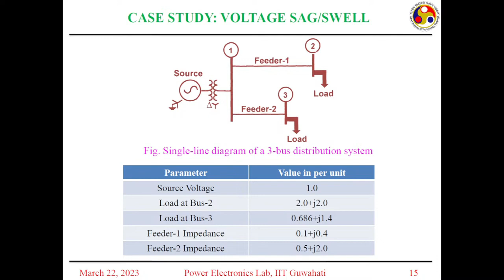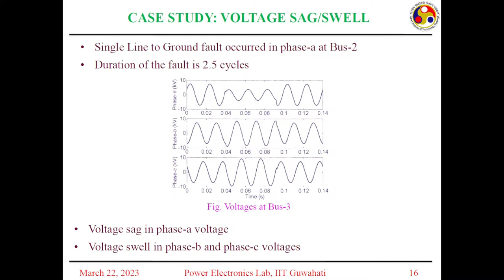This is phase A voltage, this is phase B voltage and this is phase C voltage. So there is a single line to ground fault in phase A at bus 2. Because of this we have a decrease in the voltage peak value in phase A and an increase in the voltage peak value in phases B and C. So the same fault has a different effect in phase A and a different effect in B and C. So this shows the source of the voltage sag and swell. Once the fault is cleared after 3 cycles, the voltage becomes the nominal value.